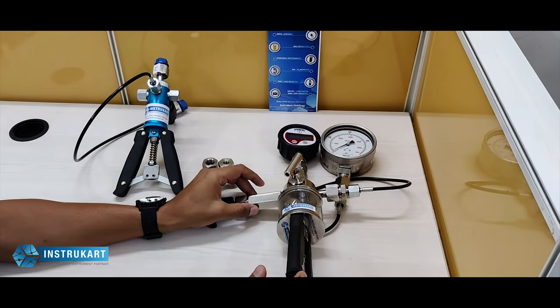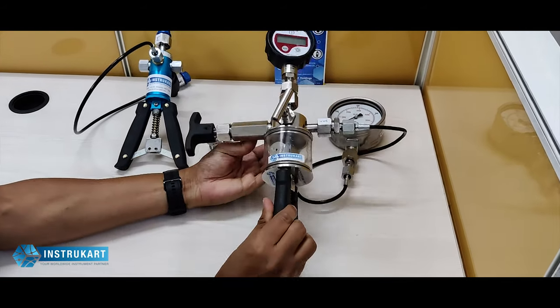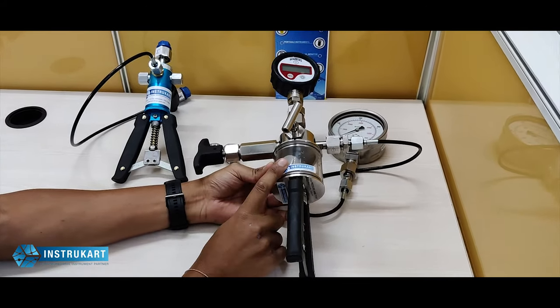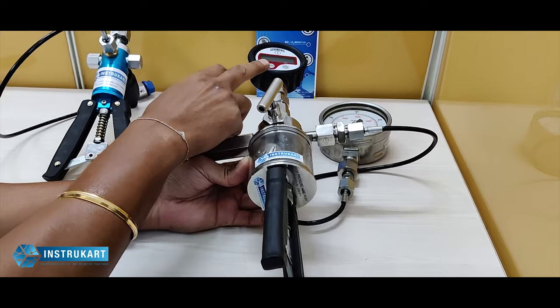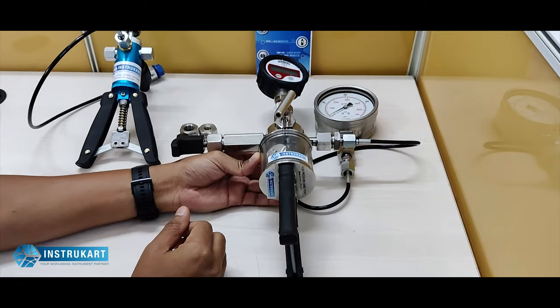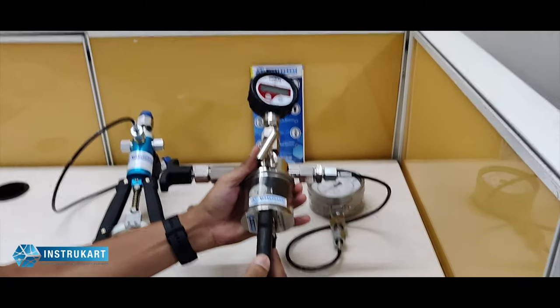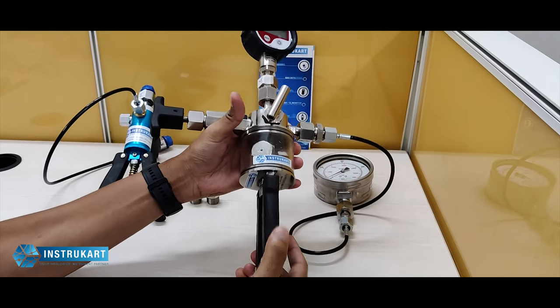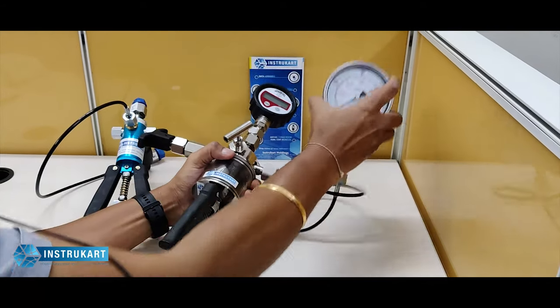Hello and welcome to Instrukart Holdings, your worldwide instrument partner. We have a hydraulic hand pump pressure calibrator used to do calibration along with a master for reference, and this can go up to 600 kg per centimeter square. This is a heavy pressure calibrator with a full stainless steel body, and this is the pump unit which is used to pump and compare between the master and the unit under calibration.